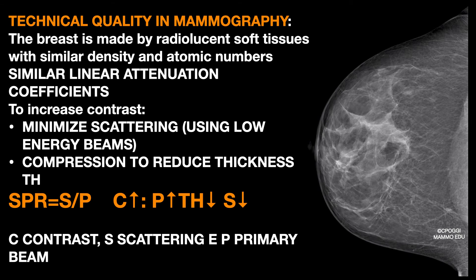The breast is an organ made of relatively radiolucent soft tissues with very similar density and atomic number. Their linear attenuation coefficient — that is to say their capacity to attenuate the radiant beam by removing a fraction of photons from it — are similar. The contrast between healthy and pathological tissue is very low. It must be increased by minimizing scattering. That is the reason why low energy beams are used in mammography, and by applying compression of the breast in order to obtain a reduction of its thickness.